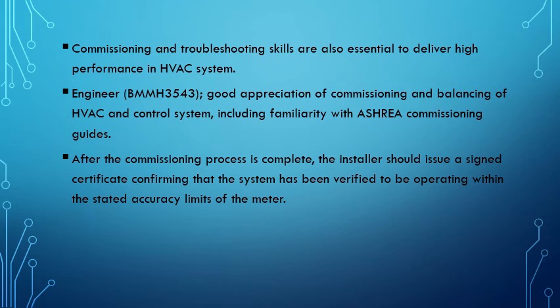So troubleshooting and commissioning skills are also essential to deliver a high performance HVAC system. So this refers back to the technician or engineer who is experienced. The engineer must have a very good appreciation of commissioning and balancing of HVAC and control systems, and must be familiar with the ASHRAE guideline for the commissioning process. So after the commissioning process is complete, the installer or the subcontractor or the contractor must issue a signed certificate confirming that the system has been verified by the consultant or the main contractor or the building owner, and then the document must be kept well, and the accuracy must be validated by them.